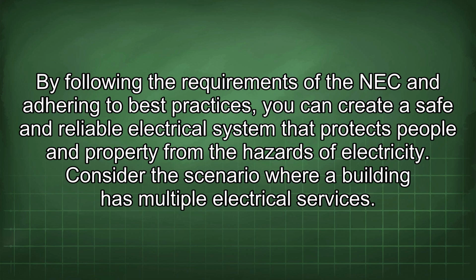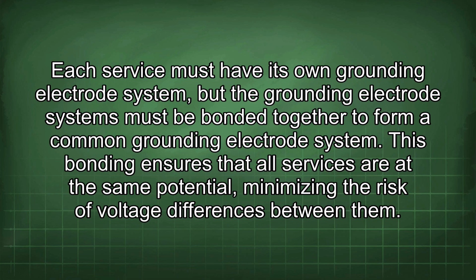Consider the scenario where a building has multiple electrical services. Each service must have its own grounding electrode system, but the grounding electrode systems must be bonded together to form a common grounding electrode system. This bonding ensures that all services are at the same potential, minimizing the risk of voltage differences between them.